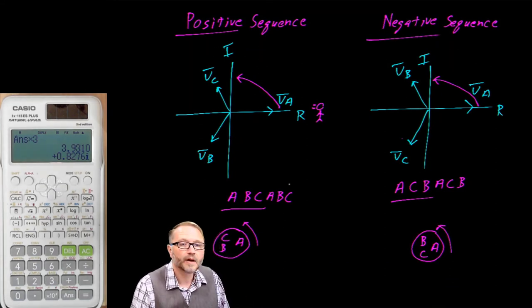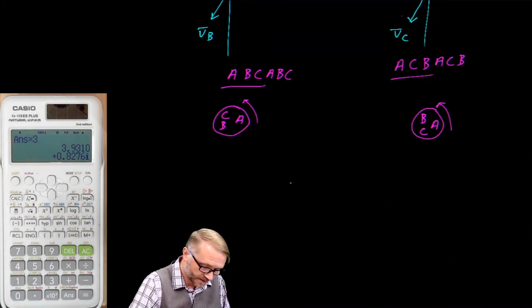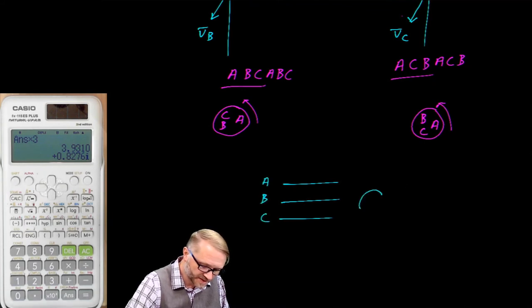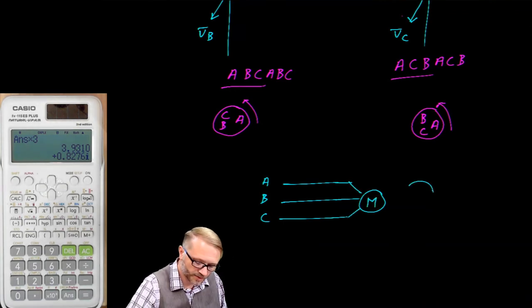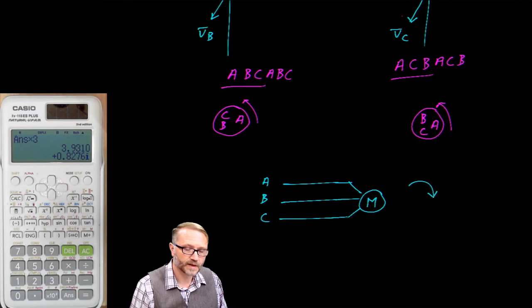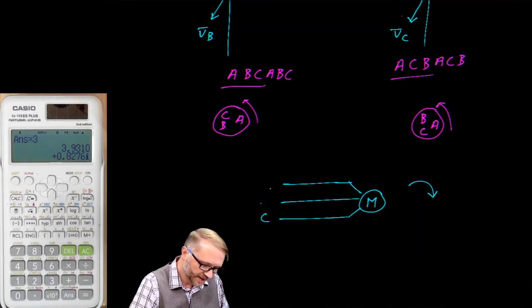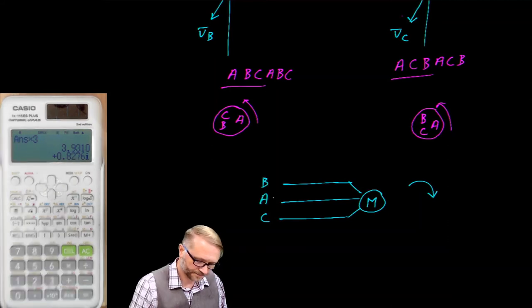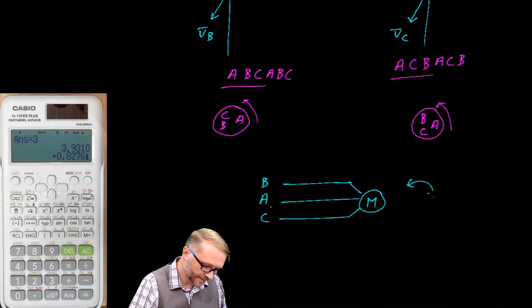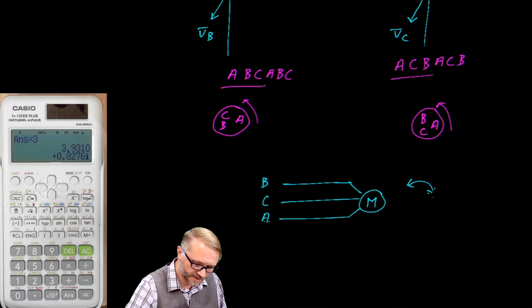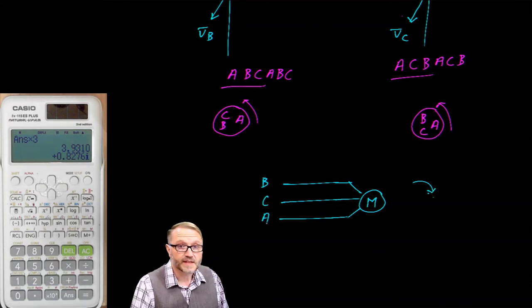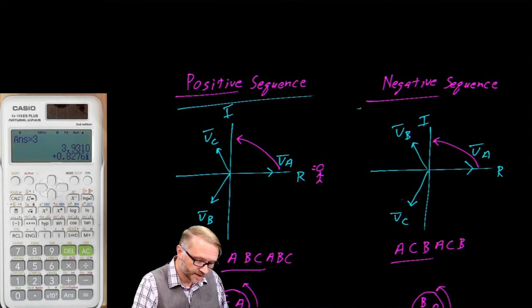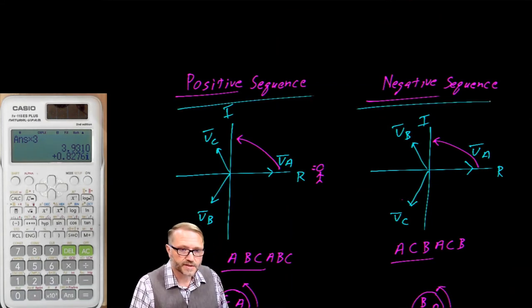With a positive ABC sequence, the motor turns in a clockwise direction. However, if you reverse any two wires, you change the sequence to ACB, and the motor turns in the opposite direction. Swap any two wires again, and it changes back. The order of the phases — the phase sequence — directly determines the direction of rotation of a motor.